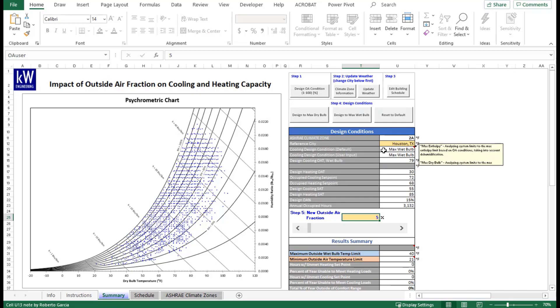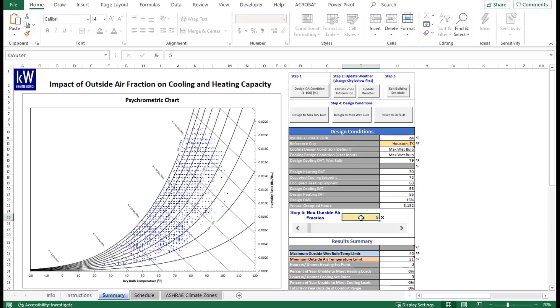The next step, step five, is now where the user gets to adjust their outdoor air fraction for how the outdoor air fraction change will impact the building. Currently, because our building is set to 15% designed, that means that our building can handle up to 15% most of the year's conditions. However, we can adjust that value in the simulation. At this point, we have it set to five, which tells us that because all these dots are blue, our building is more than capable of handling the load for the entire year.